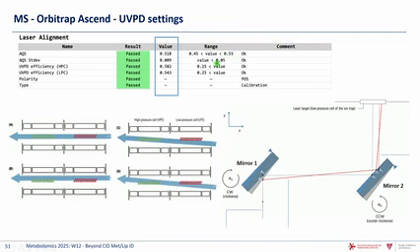If you look at the UVPD efficiency here, is the range okay with 0.25? I would say definitely no. You need to go at least 0.5. Otherwise, the laser is not efficient enough, and you will have quite a low yield of fragments from your molecule.